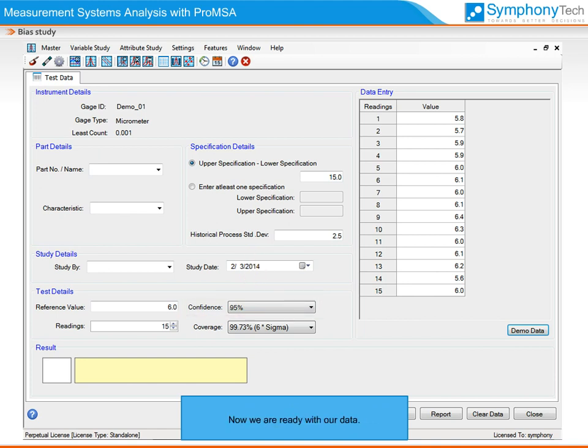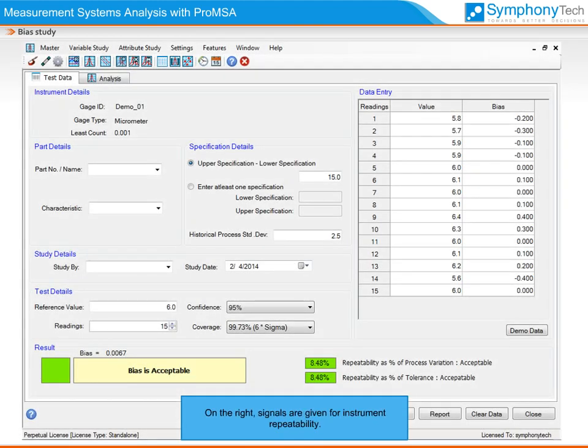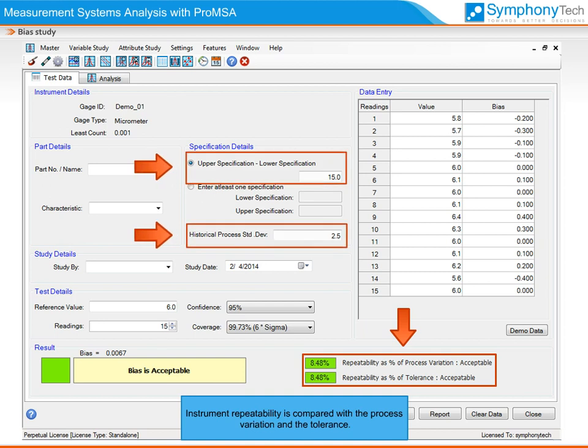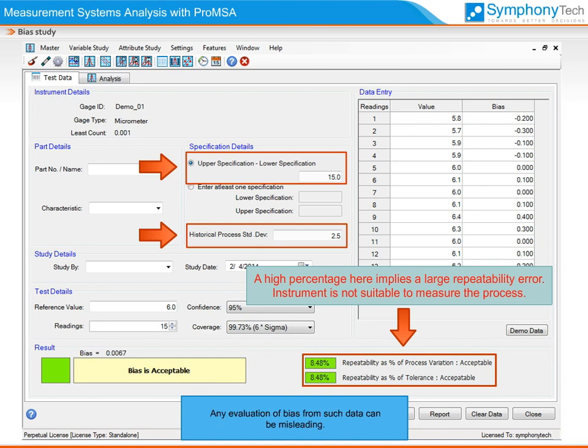Now we are ready with our data. On the click of the calculate button, Pro-MSA will evaluate your data and display results in a traffic signal format. Signals are given for instrument repeatability. Instrument repeatability is compared with the process variation and the tolerance. A high percent repeatability implies that the instrument variation is overshadowing the process variation, and the instrument may not be suitable to measure the process. Any evaluation of bias from such data can be misleading.